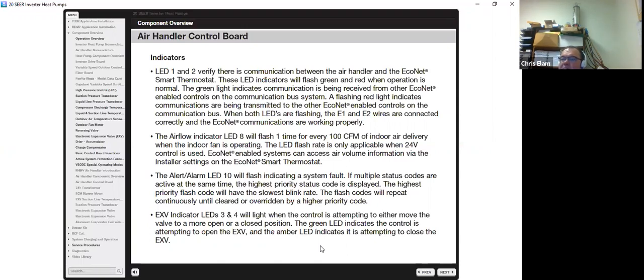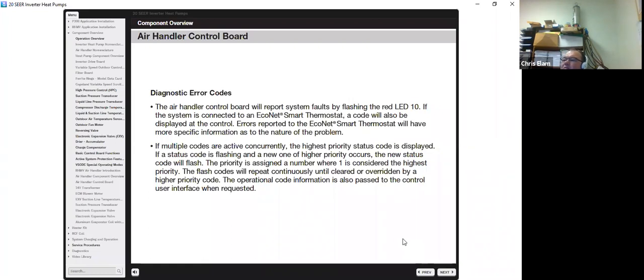If you power the unit up, at that point you'll see the green solid and the red. Once it's stabilized, you'll only see small flashes of green and red because it's only opening in small increments. The diagnostic error codes will report a system of faults by flashing on LED 10. If the system is connected to an EcoNet, it will also be displayed specifically at the EcoNet as well.